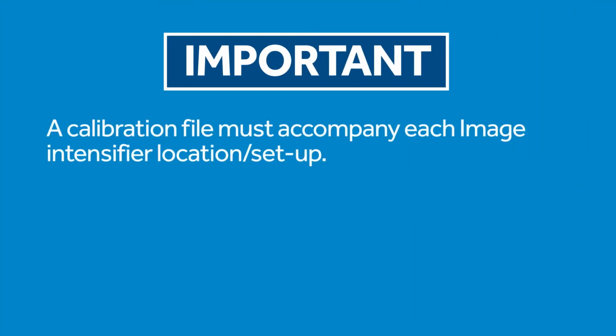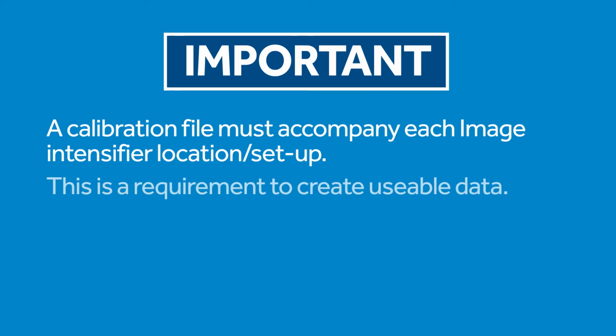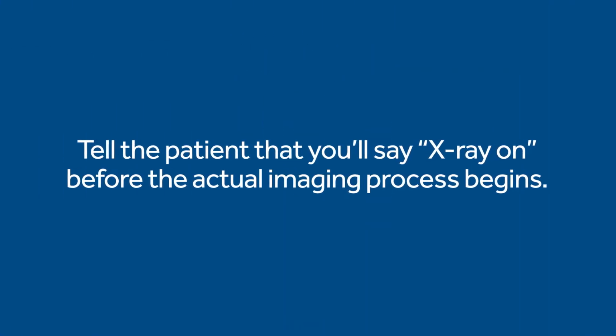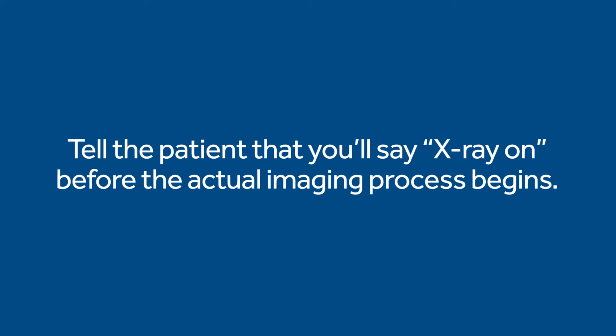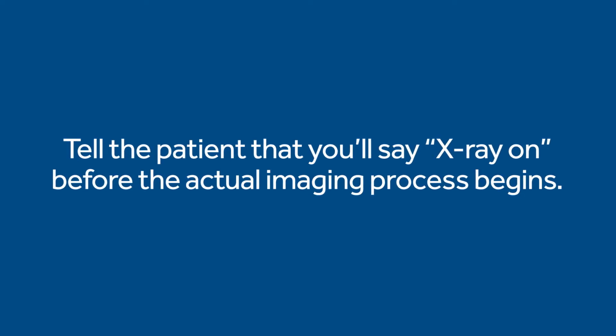A calibration file must accompany each image intensifier location setup. This is a requirement to create usable data. After the practice, provide any corrective action or feedback. Also tell the patient that prior to the actual imaging starting, you'll say X-ray on so they know when to start their arm movement.